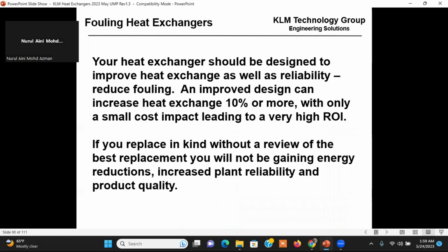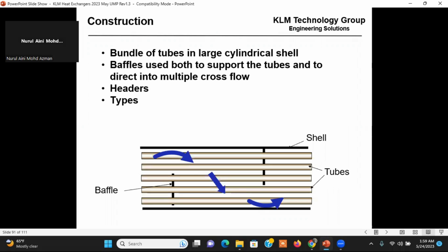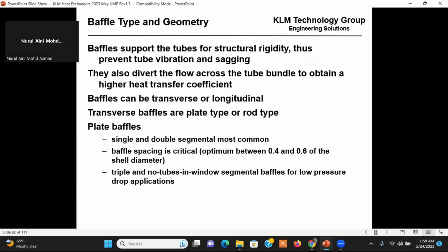We can design a heat exchanger with increased efficiency very easily. All right, so what do we want to do? What we have here are these baffles, and we deliberately put these baffles in to make the flow go around the heat exchangers. And they're a good thing. Baffles are a good thing if they're done correctly. They're a bad thing if they're done incorrectly.